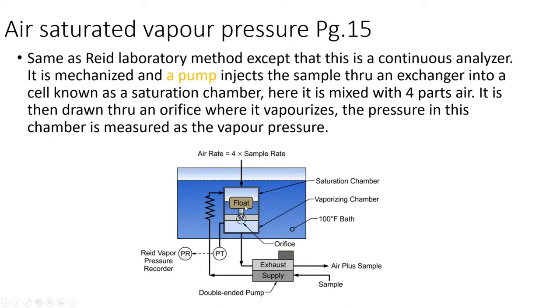The online version of the air-saturated vapor pressure test is the exact same process as the Reid laboratory method, except it's a continuous analyzer. A pump injects the sample through an exchanger into a saturation chamber sitting in a water bath at 100°F, where it is mixed with four parts of air. The sample is then drawn through an orifice where it vaporizes, and we measure the pressure off the side of the chamber through a pressure recorder. Key things to remember: it has a pump, an orifice, it's in a bath, and it uses a four-to-one air-to-sample ratio.